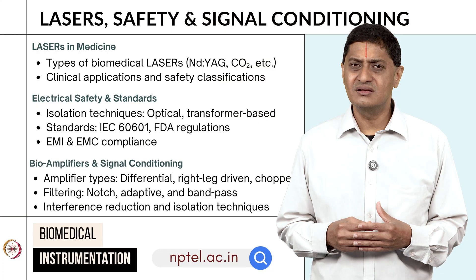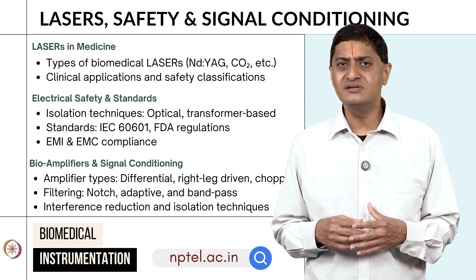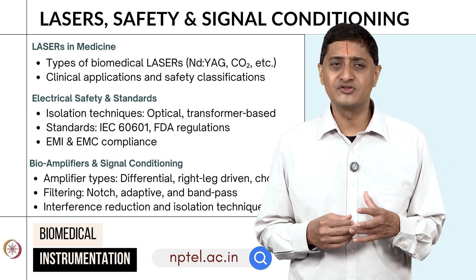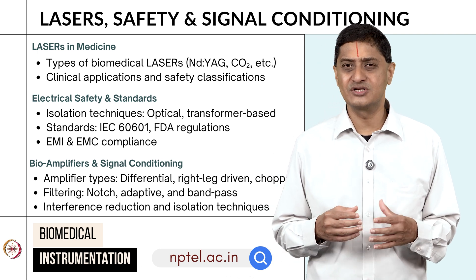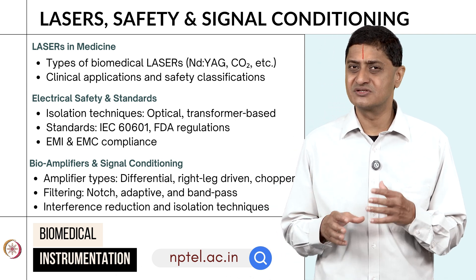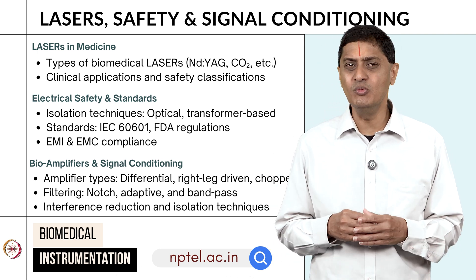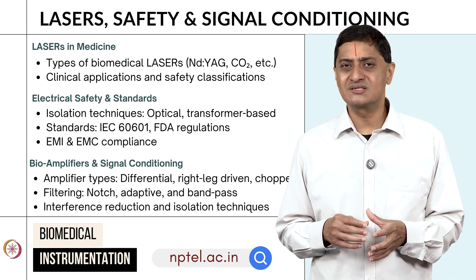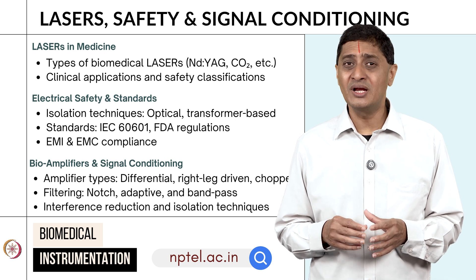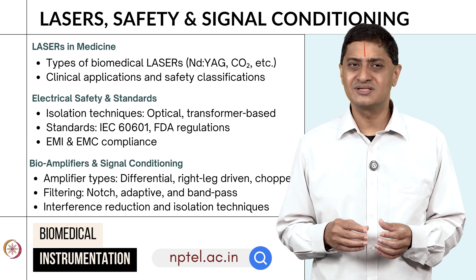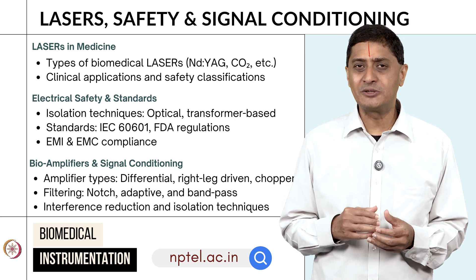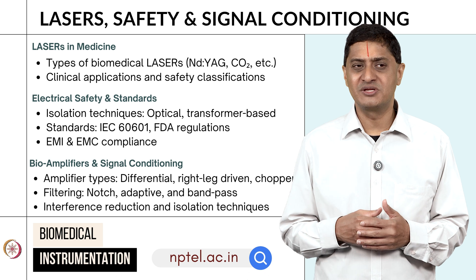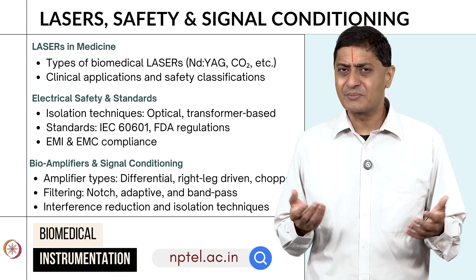For safety, another critical topic is electrical isolation from the patient, because these instruments are going to be used on humans. There are various ways through which we can provide isolation — optical isolation methods and transformer-based methods.